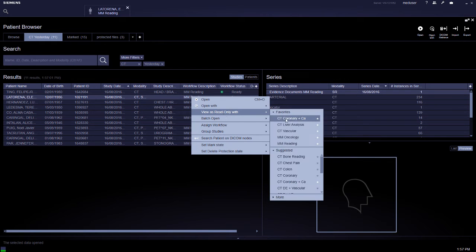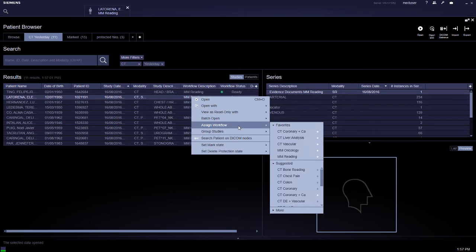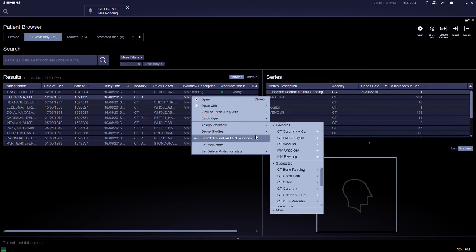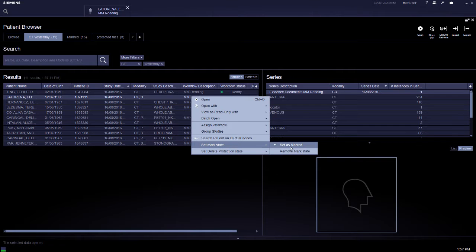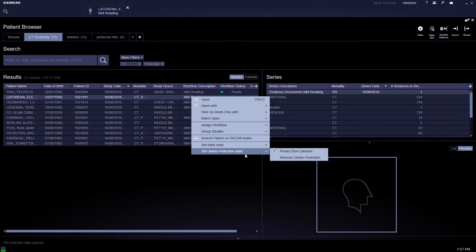Read Only is to open without any saving of results. Assigning is to just assign a workflow without opening. You can also set it as a mark, and set the series or patient data to protect from deletion from the syngo.via server.